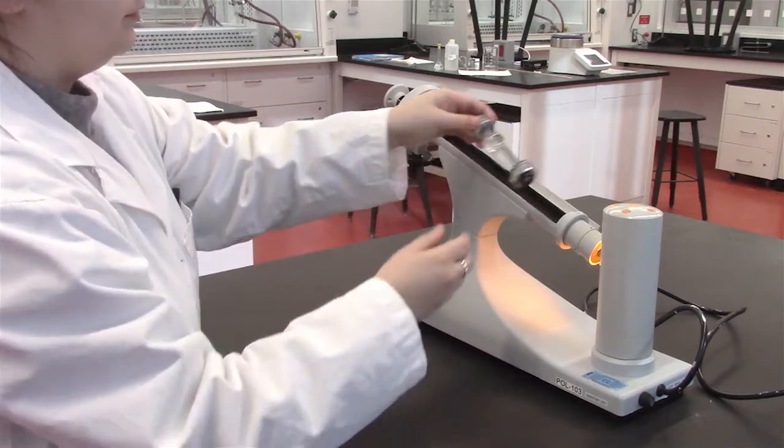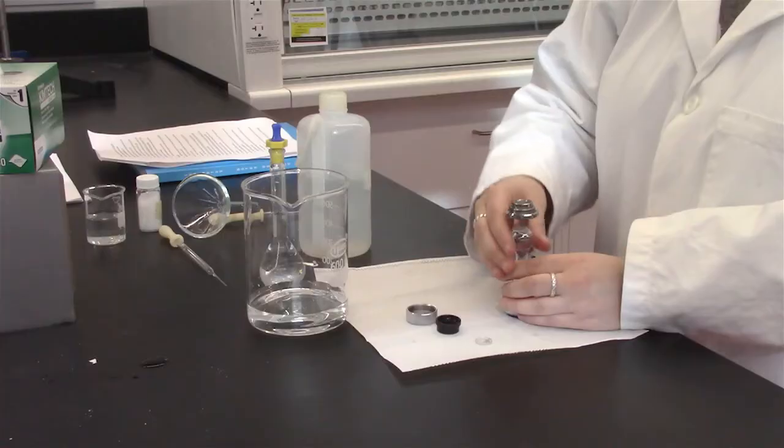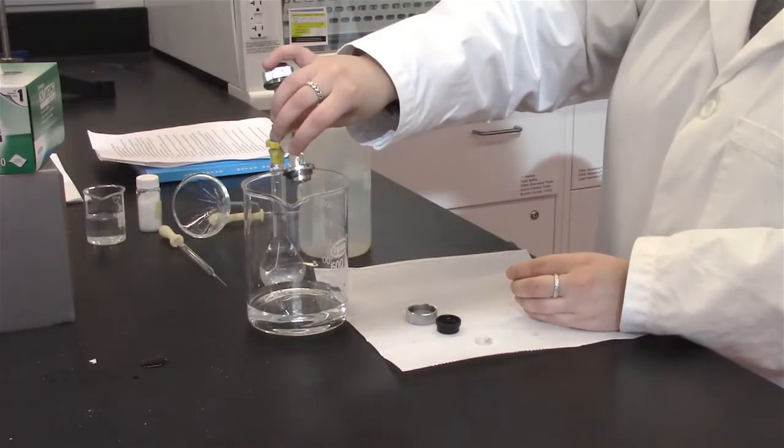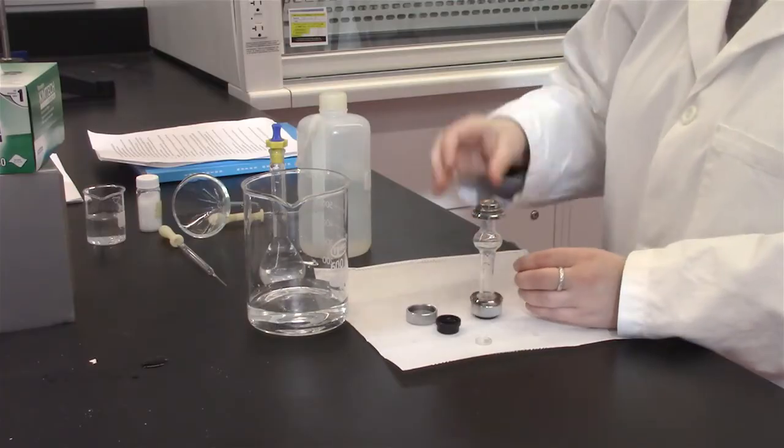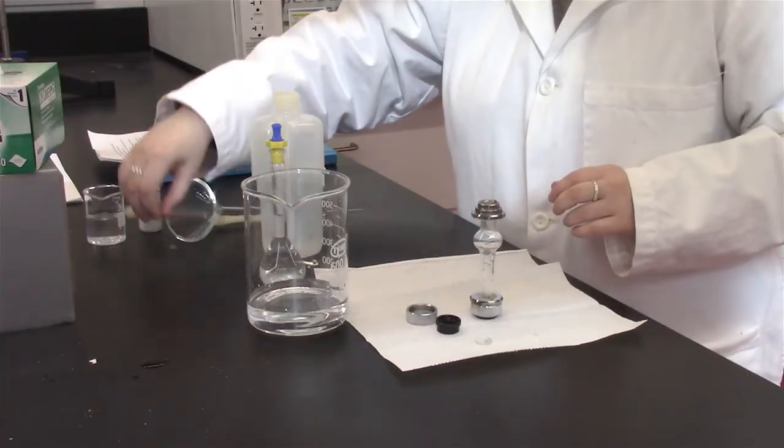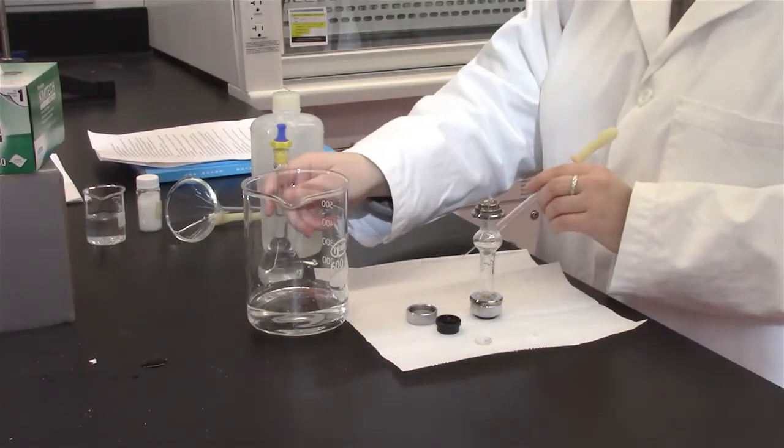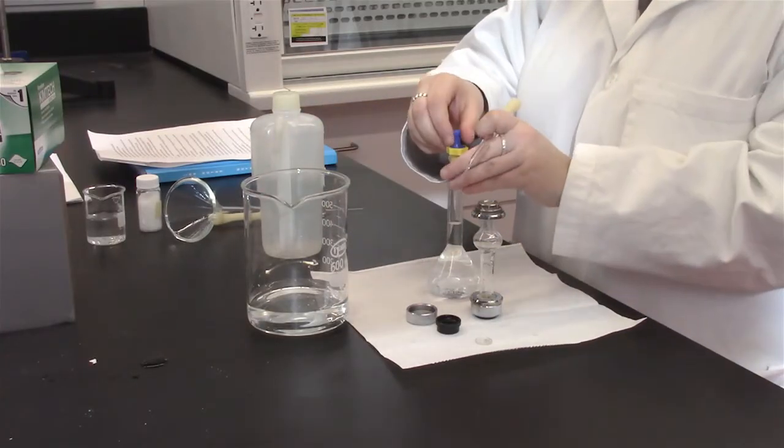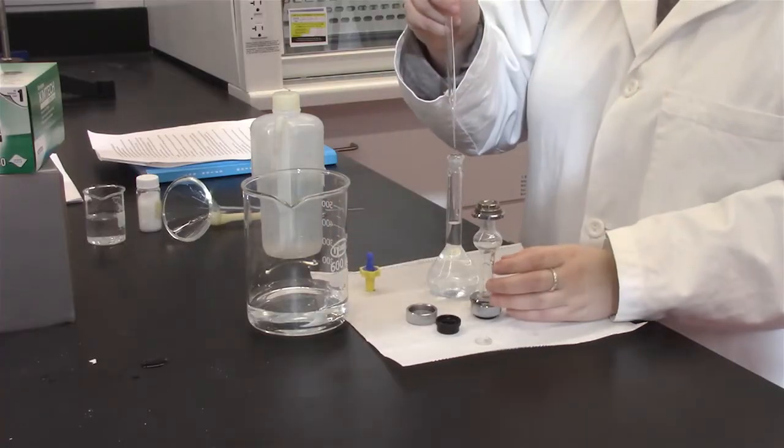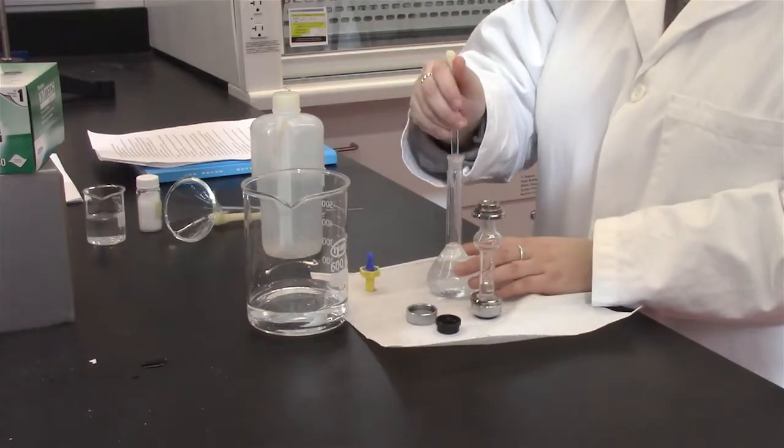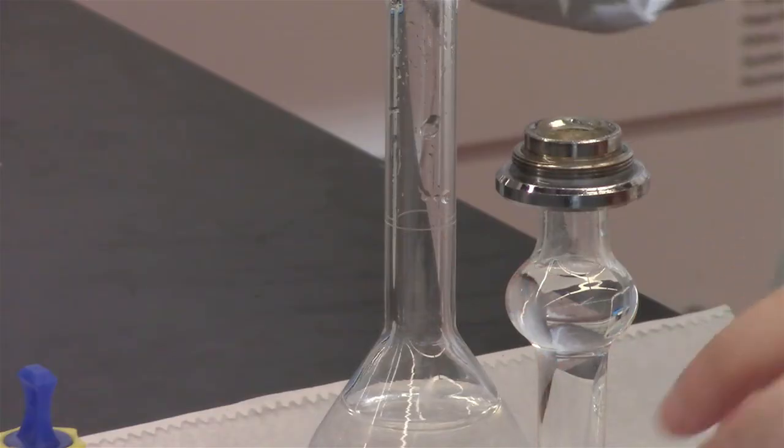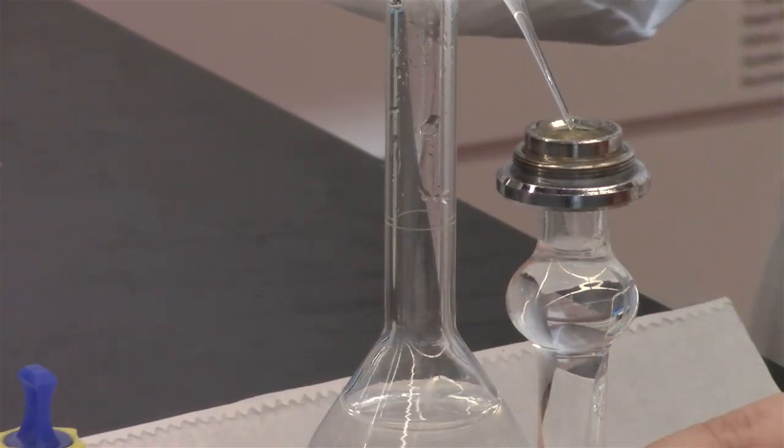Next, discard the deionized water in the waste beaker and fill the sample holder with your prepared solution. Ensure minimal bubbles are present or, if they are present, they are present in the curved portion of the sample holder as shown previously.